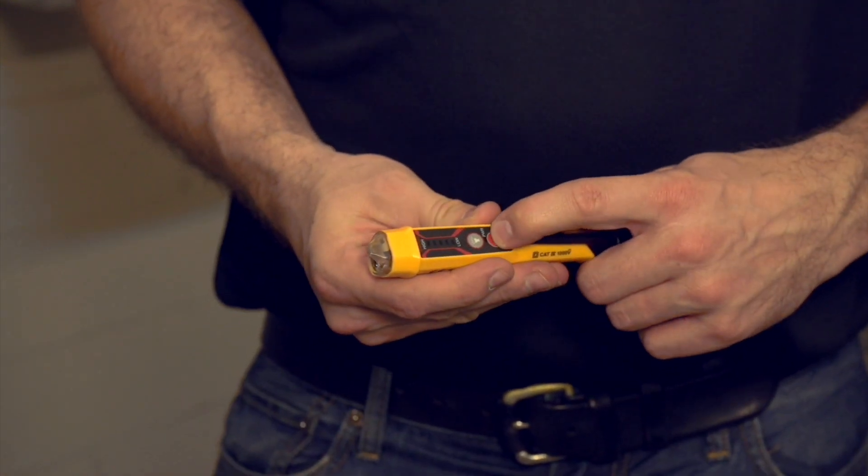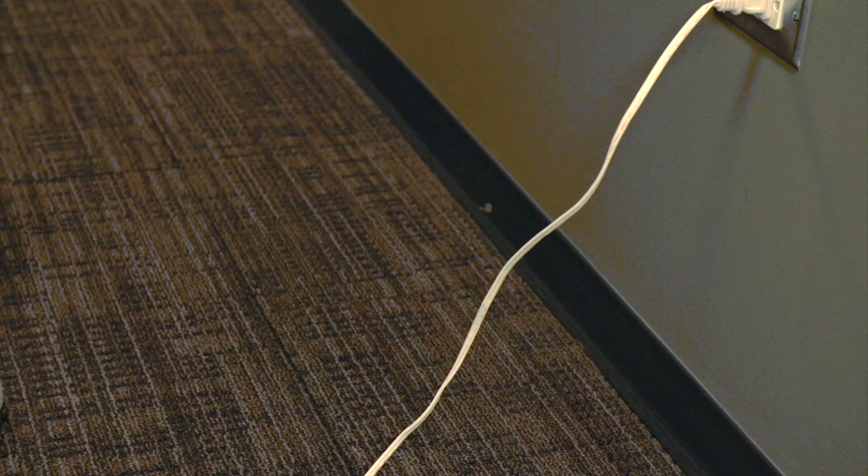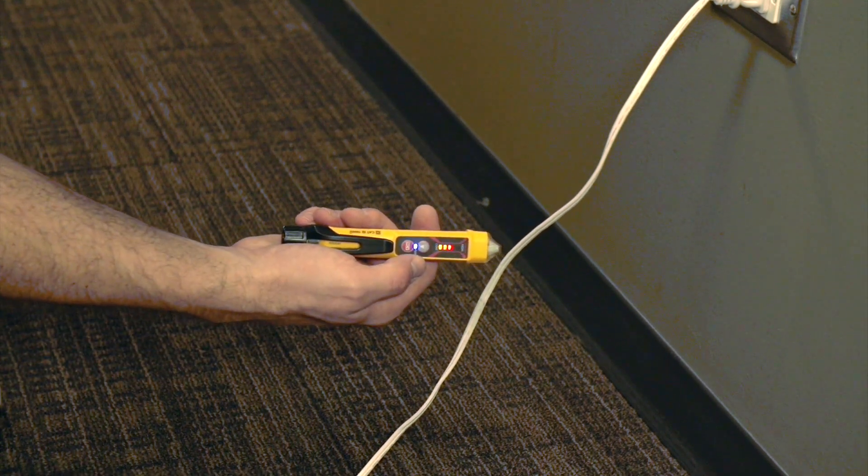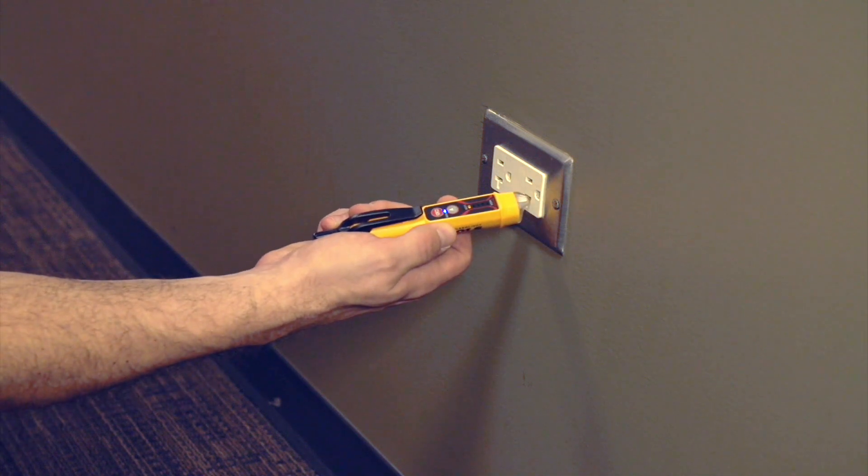Best practice in testing with non-contact voltage testers consists of three steps. First, test a known live system such as a cord of a lit lamp or an electrical receptacle or outlet to verify the tester is functioning correctly.